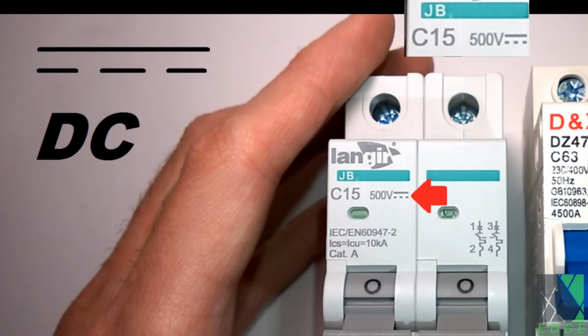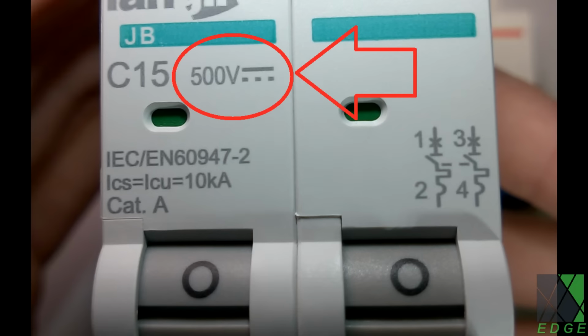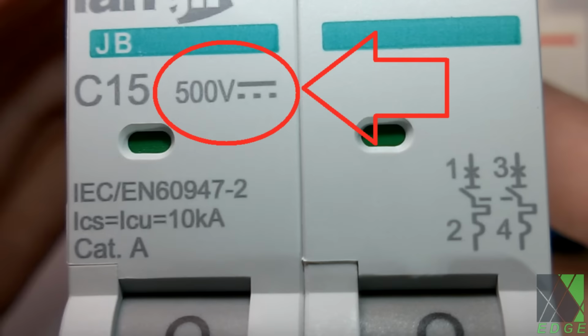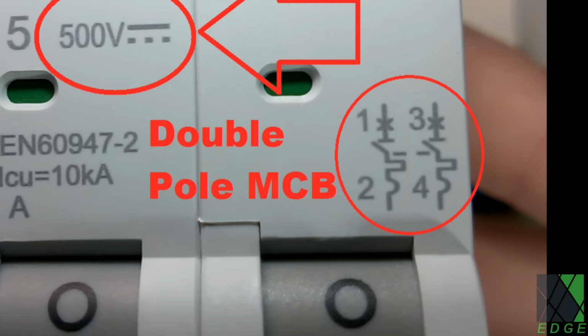On the left we have a symbol of a straight line over a dashed line, the symbol for DC or direct current. In this case the breaker is rated up to 500 volts DC, but I would not operate this breaker at its maximum rating. Furthermore, this rating is only at double pole, meaning each side of the breaker can handle 250 volts, so this 500 volt rating only applies when the circuit breaker is breaking both the positive and negative side of the feed.